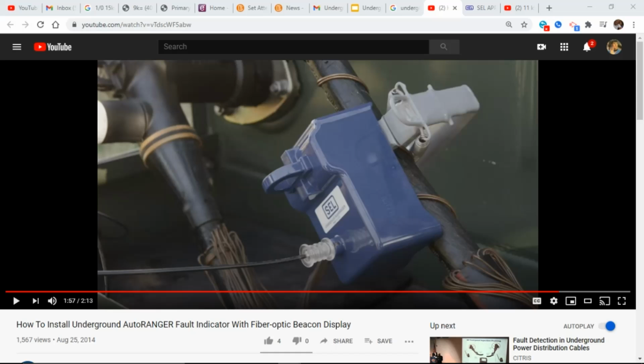If I go down here to the lower left, stand by a second, then I'll let you go with your question. If you look down here at the lower left, there's a neutral wire coming up inside the jacket and then back out. If I put my fault indicator over all of it, it will work because I have the neutral conductors going in one direction and out the other. That's called neutral canceling. It will still work. Does that make sense now? And go with your question if you've got one. Yeah, it makes sense now. I got you. Okay, good deal.